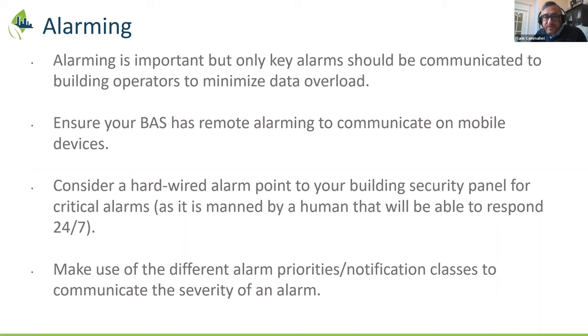That's why I'd like to stress that only key alarms should be communicated to building operators, to minimize this data overload. When we work with clients, we often try to say put the top five or top ten, because otherwise the operators become overwhelmed and desensitized afterwards. They won't even pay attention to alarms.